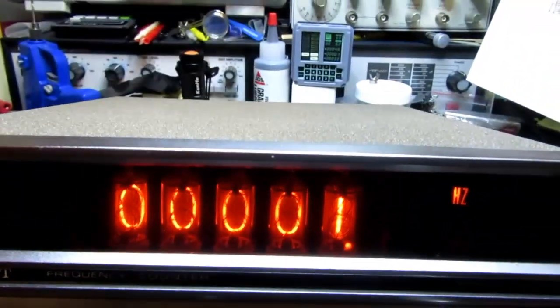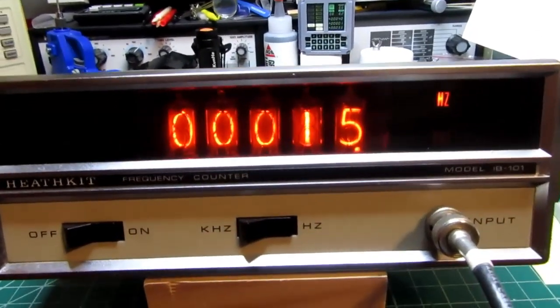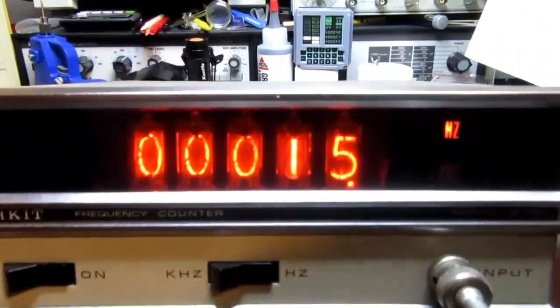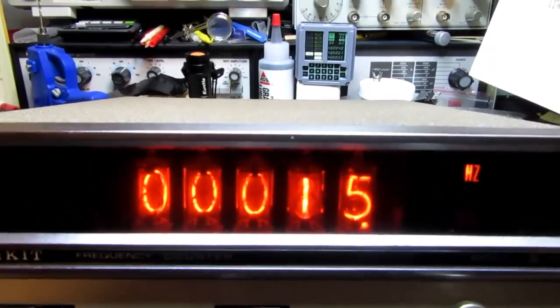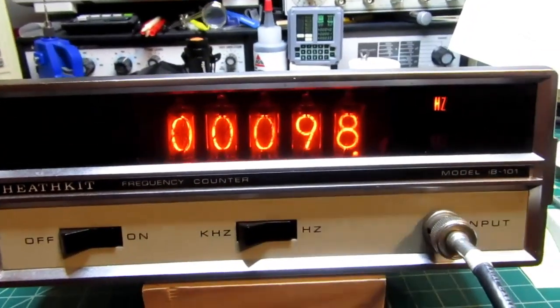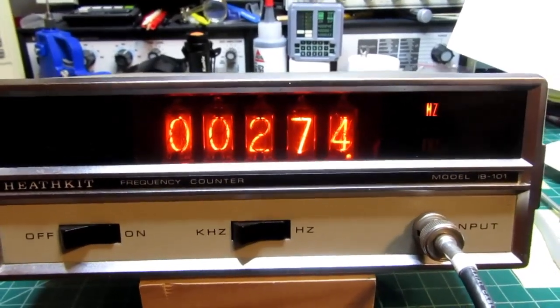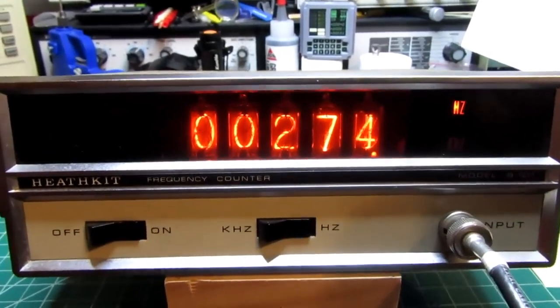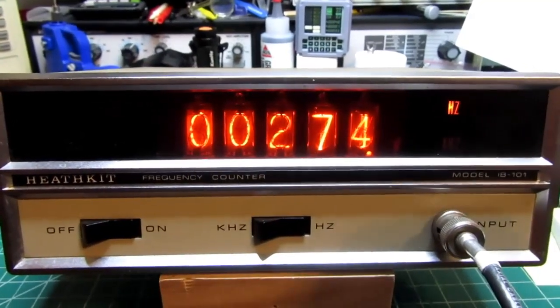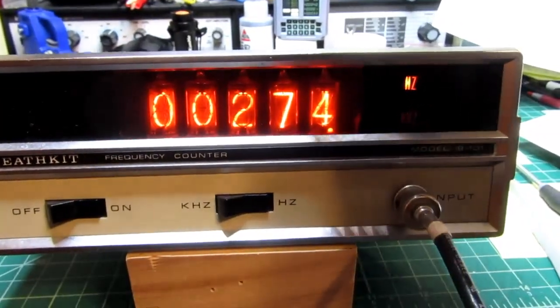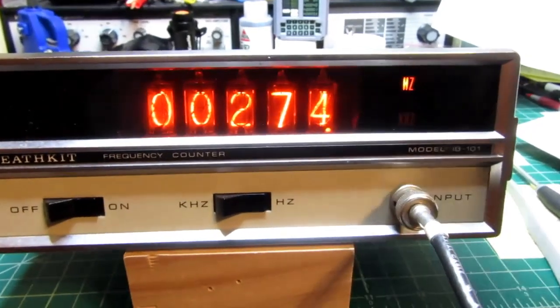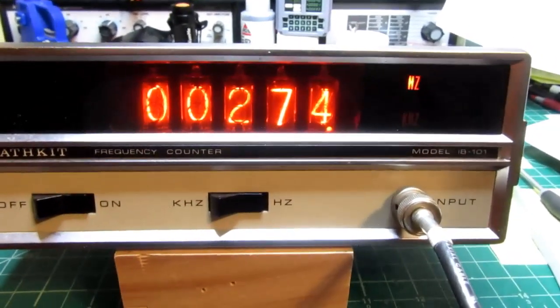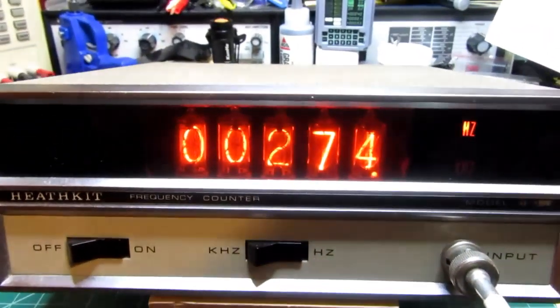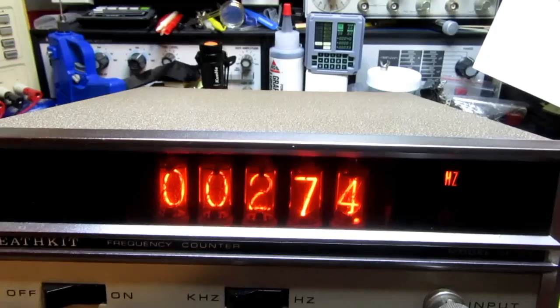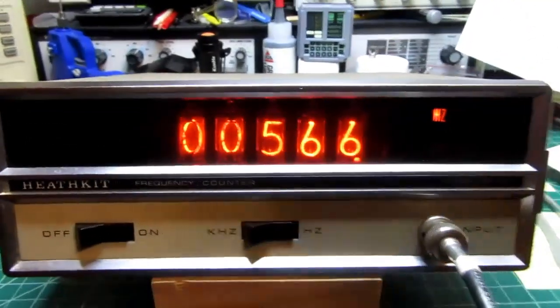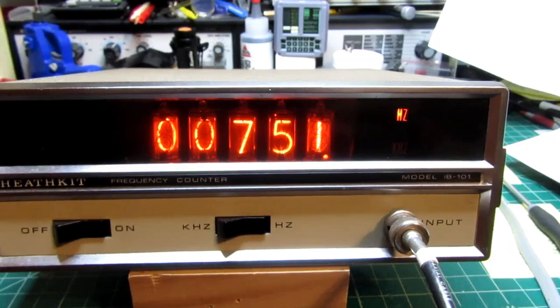Let's go up to 15 hertz, right on the money. Let's go to 274 hertz. It always is asynchronous with the input signal, so if I happen to change the frequency right in the middle of a count cycle here, you'll get 1 second's worth of inaccurate data before it takes another count and gives you the correct number. Let's put in 751 hertz. One inaccurate, then 751.